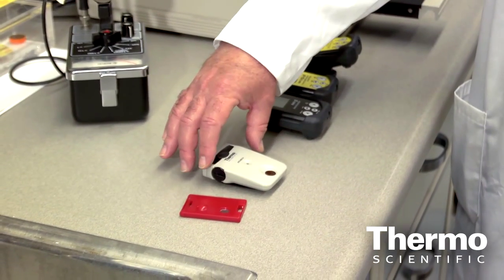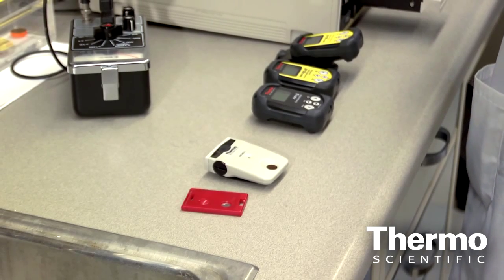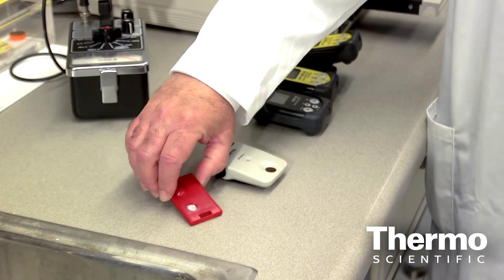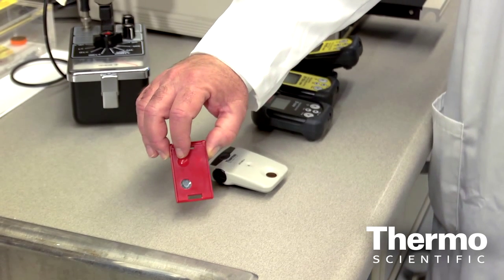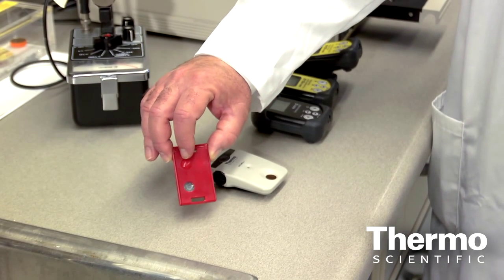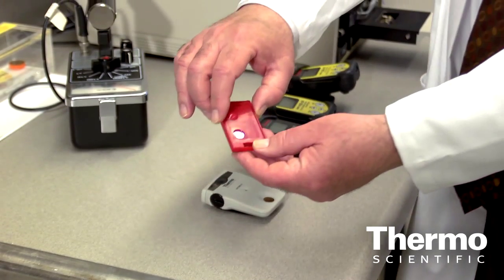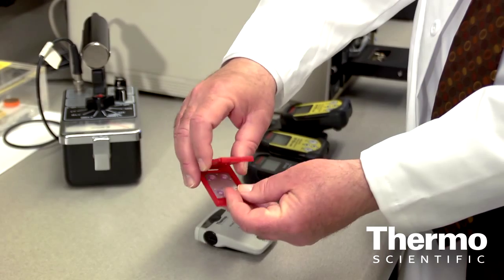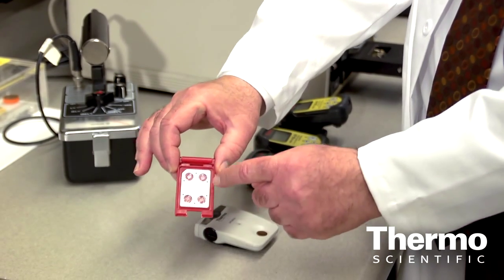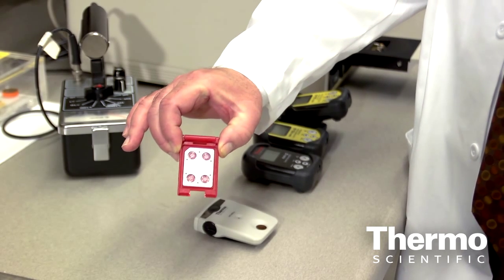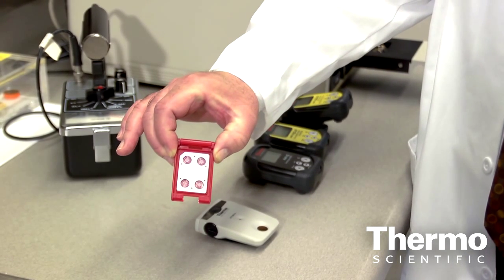These are personnel dosimeters which are used by radiation workers to monitor their personal dose. This type is called thermoluminescence dosimeter or TLD. It's made of aluminum card which has four crystals and it's called a passive dosimeter. It means that it has to be processed to be able to extract the dose information.